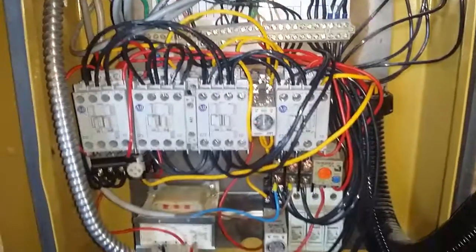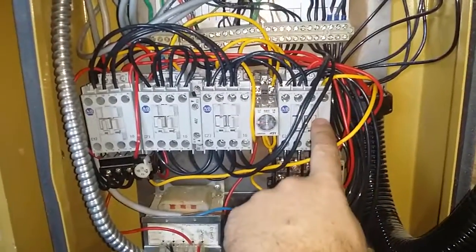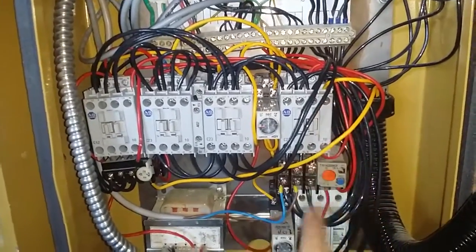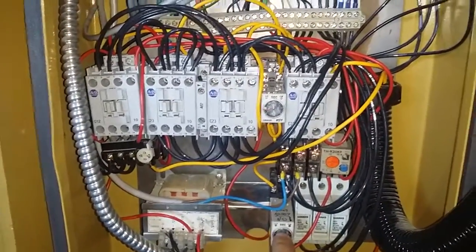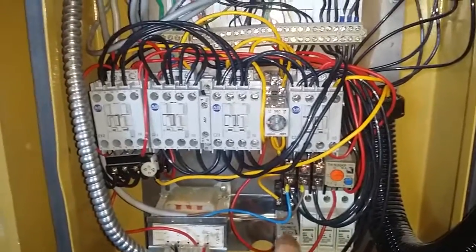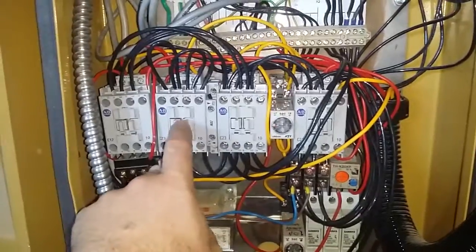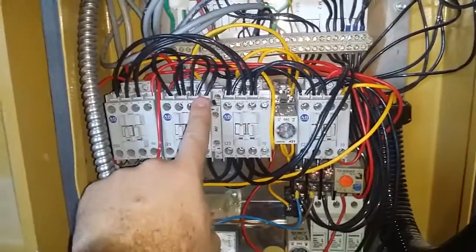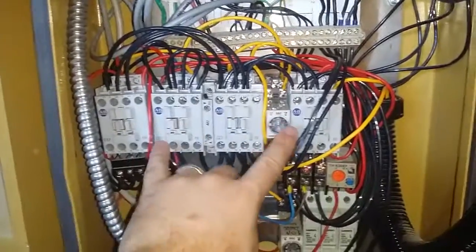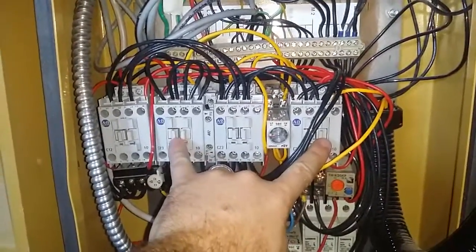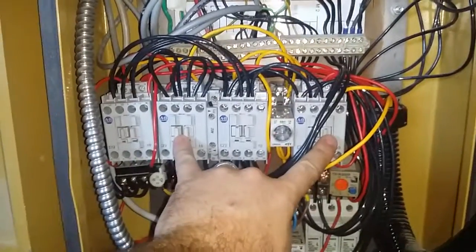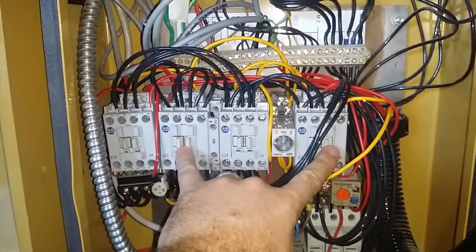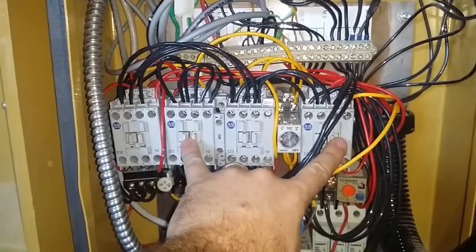You hit the control, it energizes this relay, and the control circuit for it energizes this relay, just so there's a split second time difference, which powers on this guy, which you can see is just jumped together. That's a star formation. So these two come on about roughly the exact same time, and that is the Y.